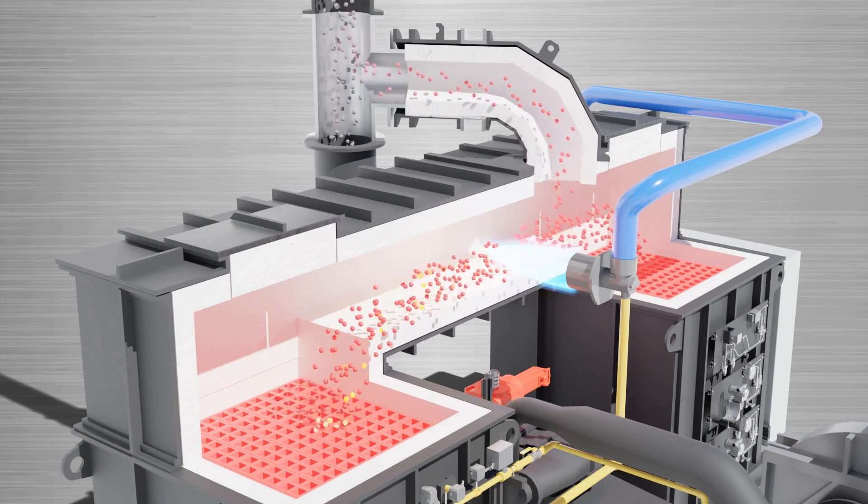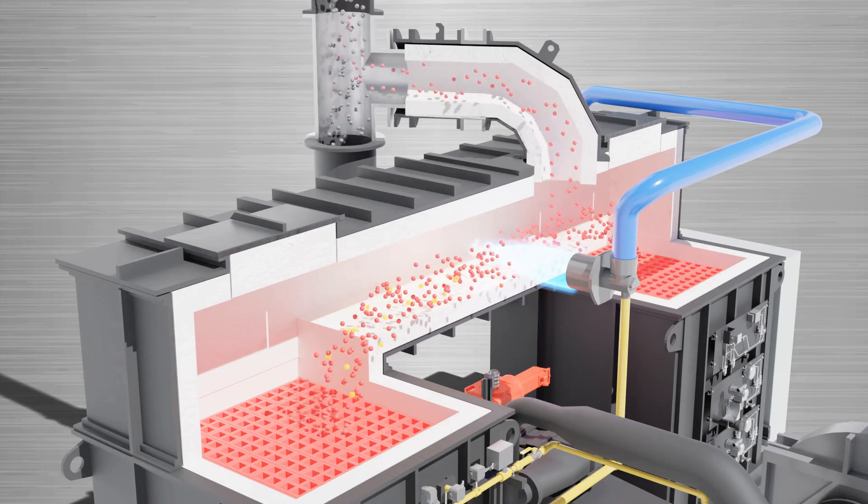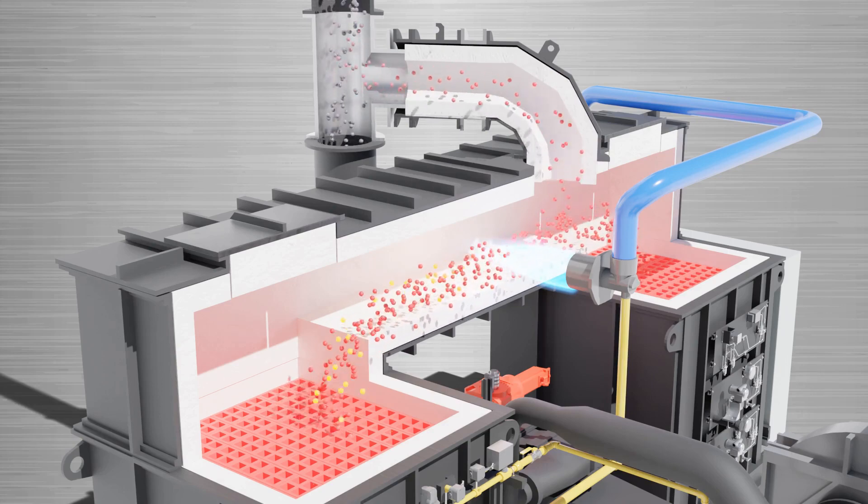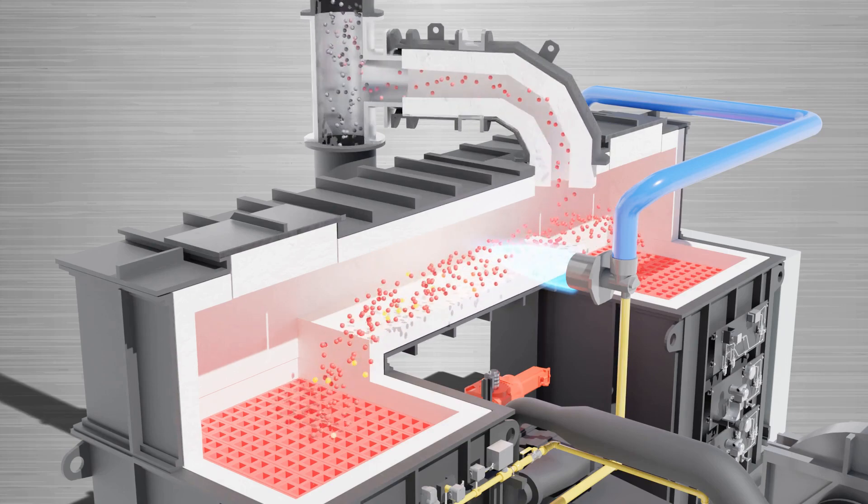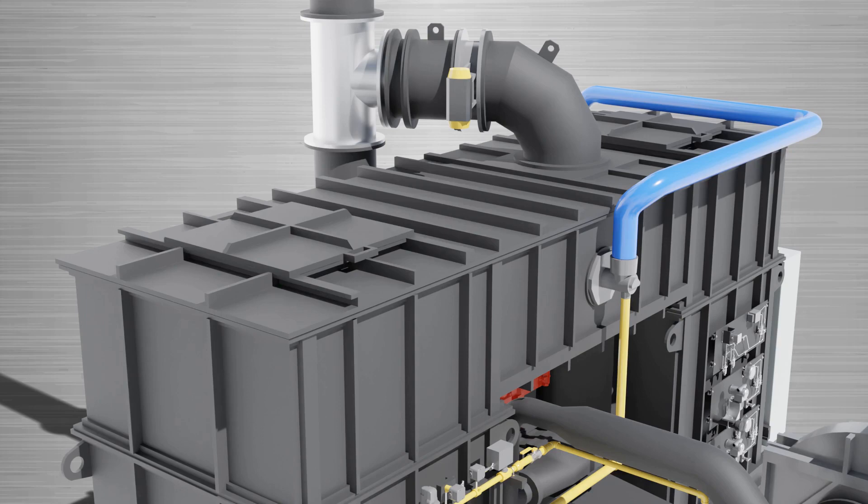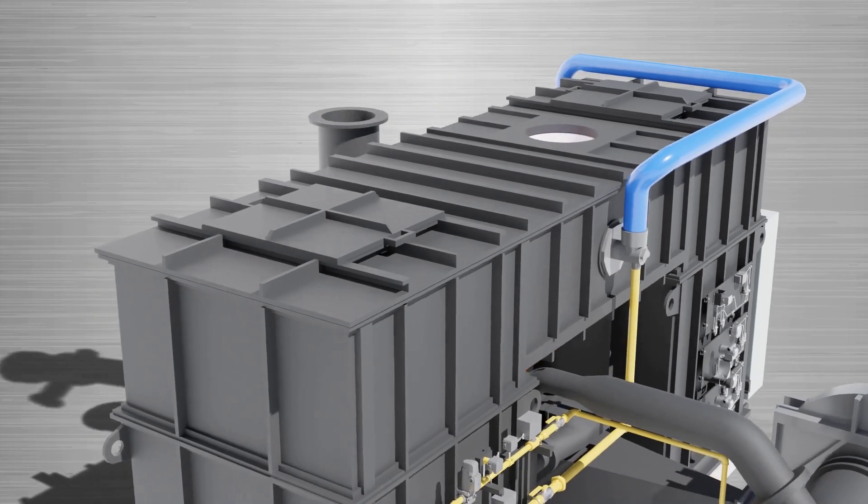The hot gas bypass damper allows a fraction of the hot flow to bypass the recovery chamber. This decreases the overall energy recovery of the system. It allows for safe and stable operation at times when high heat release would otherwise overheat the system.